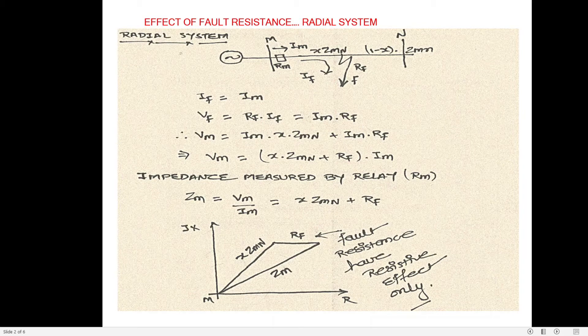In this session I am considering the effect of fault resistance on distance relay performance using two systems. First, a simple radial system for conceptual clarity. Then a more complex system involving multiple sources. We consider one source behind bus M and one at bus N. In the first simple system there is one source behind bus M, a second bus N, and a transmission line connecting them with total impedance ZMN.